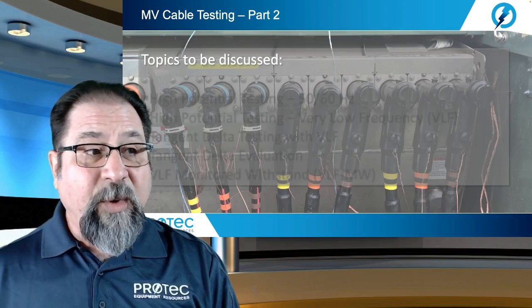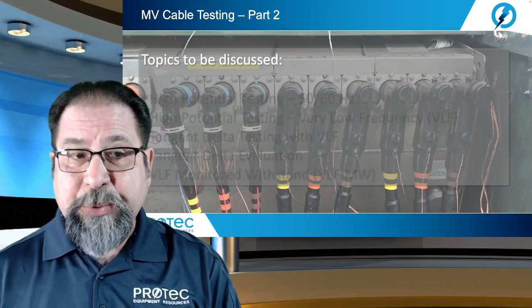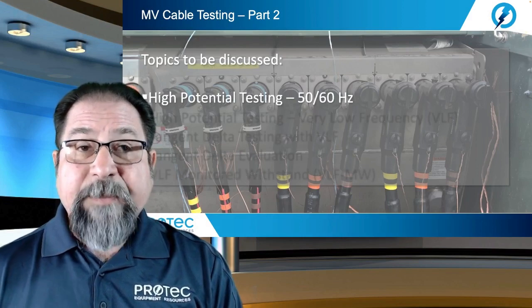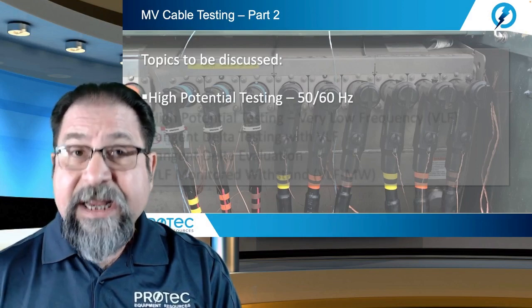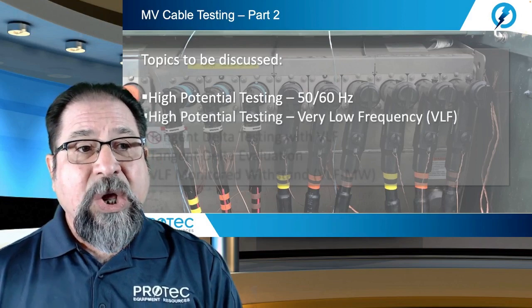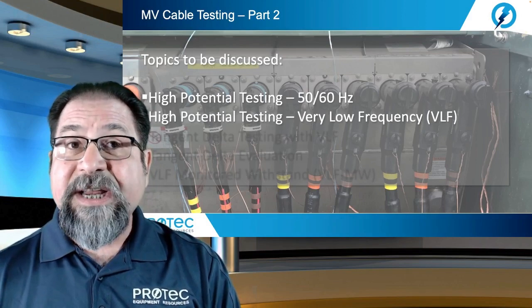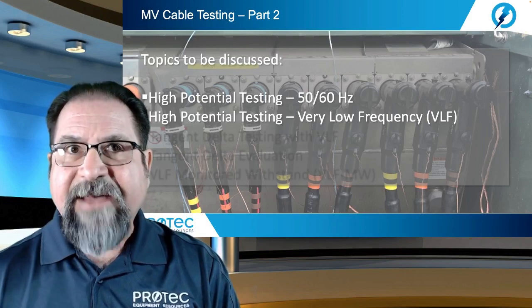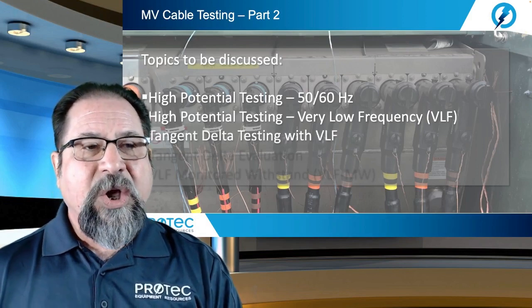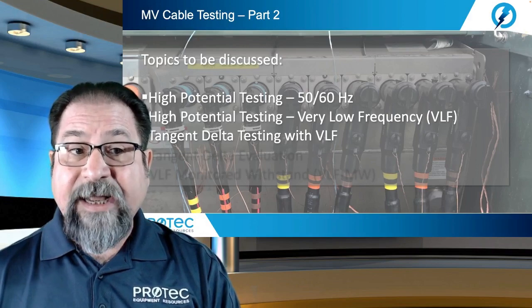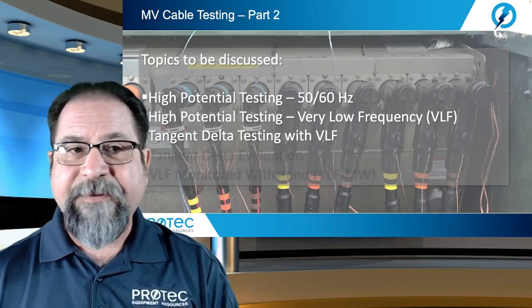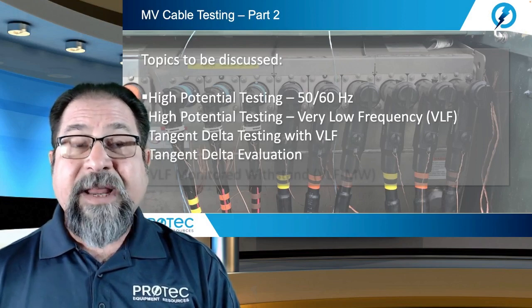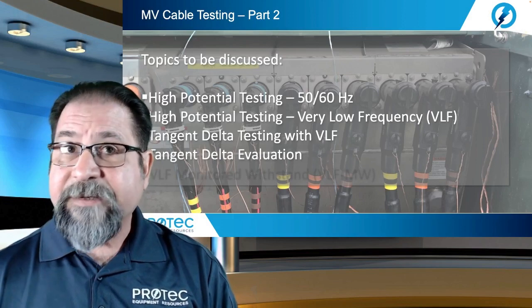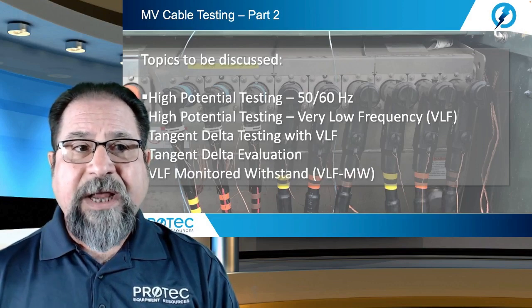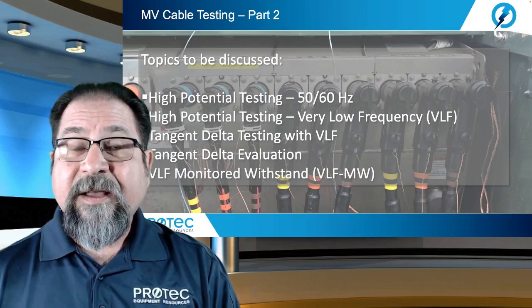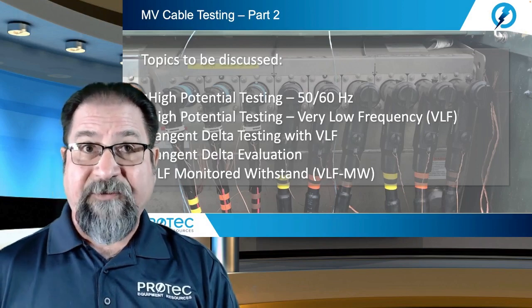So, topics that we are going to be discussing in part two will include high potential testing using power frequency, 50 or 60 hertz. We will take a look at high potential testing using very low frequency or VLF methods. We will take a deep dive into tan delta testing using the VLF. We will talk about evaluating tan delta results and also the use of monitored withstand testing at VLF, or very low frequencies.